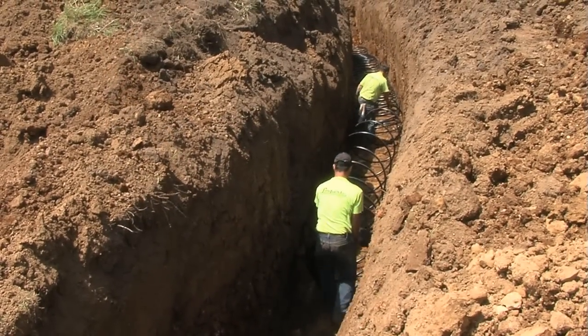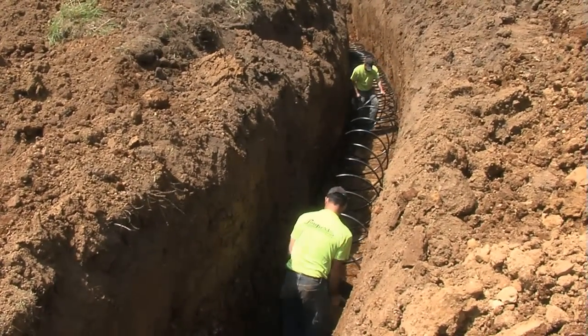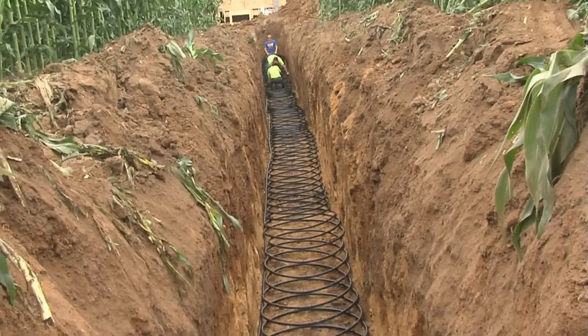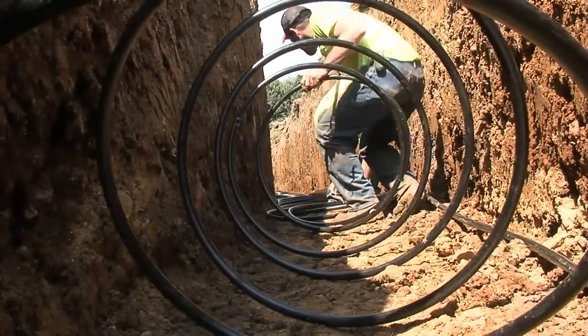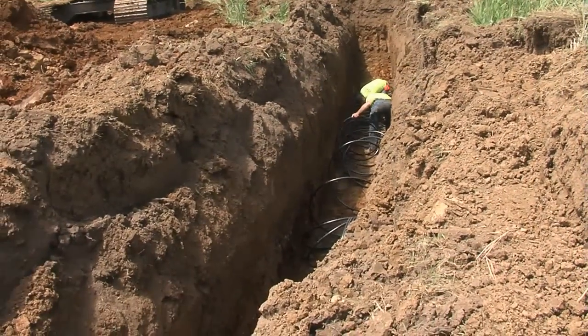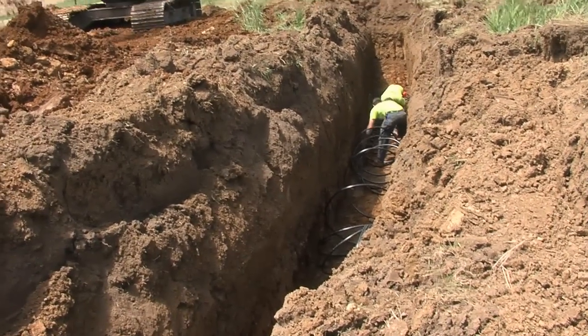In horizontal geothermal ground loops, several hundred feet of pipe is buried 8 feet deep in a trench and backfilled. A typical horizontal ground loop will see about 400 to 600 feet of pipe per each ton of heating and cooling. Because of the amount of trenching involved, horizontal ground loops are most commonly used for new construction.